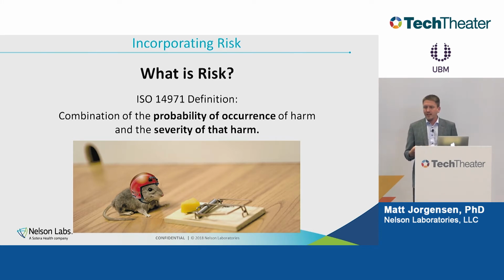If, on the other hand, a device has some sort of common problem where maybe little flakes of the device break off and are permanently left in the body, that's something we would consider when making a biological evaluation plan. So we want to address risks, but keep in perspective the probability of occurrence and how severe that harm would be.